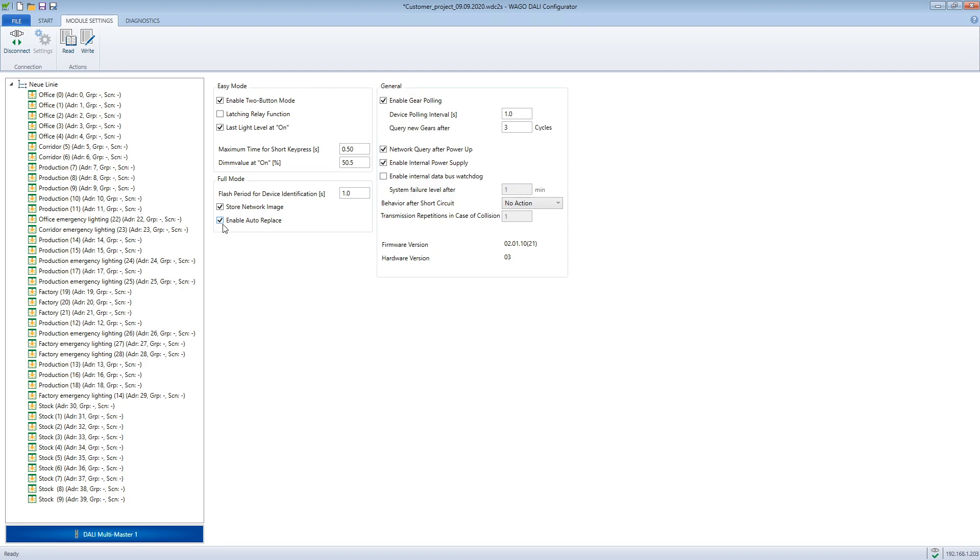Now the defective device can be removed and replaced by a new one that has no address. That no address is available should be checked in advance. The module recognizes that an address is missing and a new control gear without an address is on the bus and assigns the missing address to the new device. Groups and scene settings are also transferred to the new operating device.